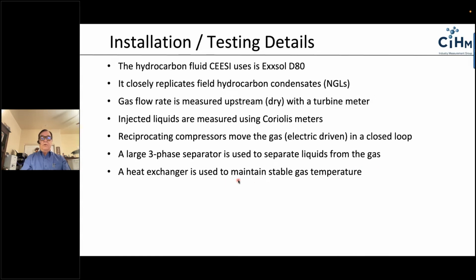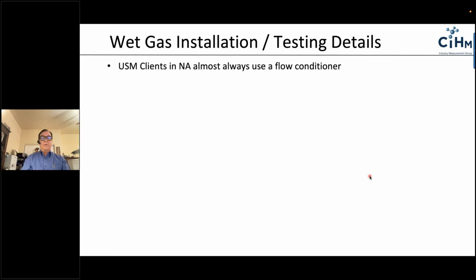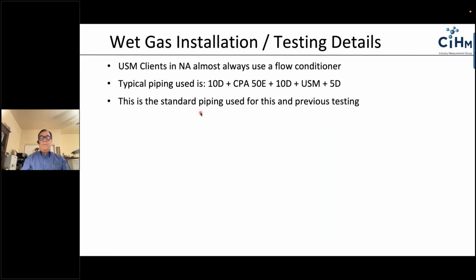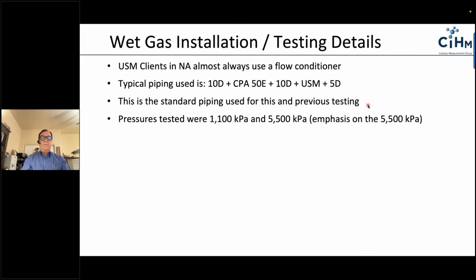They use a heat exchanger to maintain stable temperatures to help reduce the uncertainty, as we're putting a lot of energy into this recirculation system with the compressors. Ultrasonic meters in North America typically use a flow conditioner. So to replicate the previous testing the clients have done, we used a 10D, a 50E, and a 10D, along with the ultrasonic meter, and then of course the traditional 5D downstream. This is standard piping, and it's been very common in the industry, and we'll talk about some short coupled piping toward the end. But all this testing was done with the traditional 10D, 50E, 10D piping.